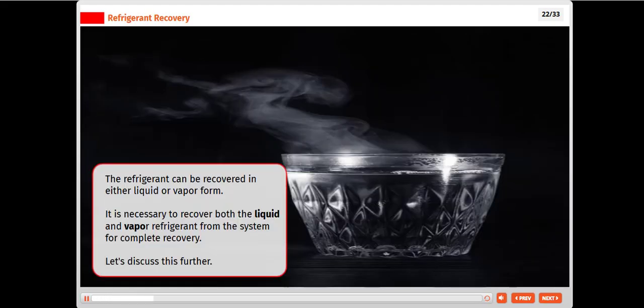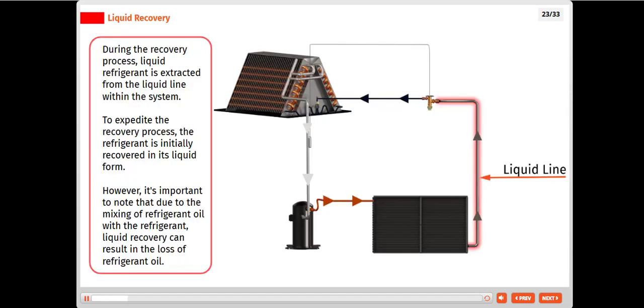The refrigerant can be recovered in either liquid or vapor form. It is necessary to recover both the liquid and vapor refrigerant from the system for complete recovery. Let's discuss this further. During the recovery process, liquid refrigerant is extracted from the liquid line within the system. To expedite the recovery process, the refrigerant is initially recovered in its liquid form. However, it's important to note that due to the mixing of refrigerant oil with the refrigerant, liquid recovery can result in the loss of refrigerant oil.